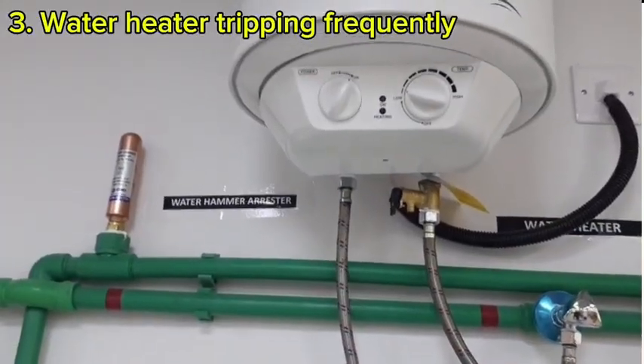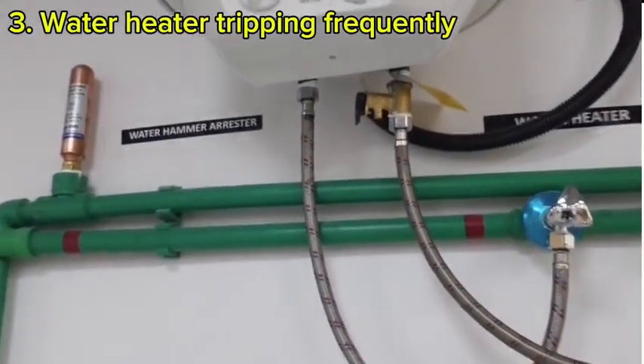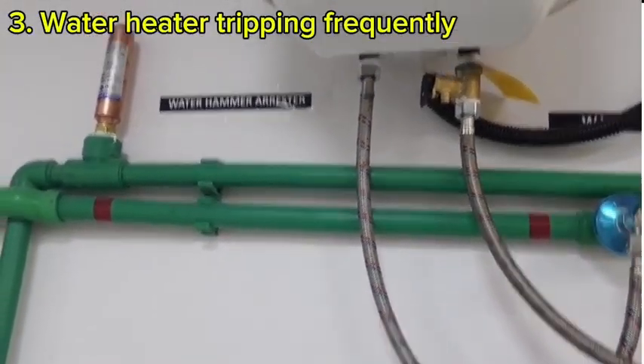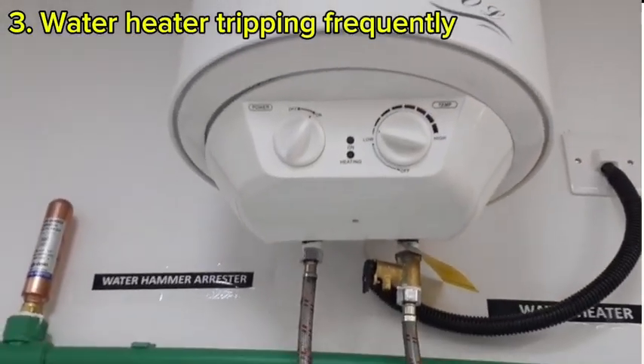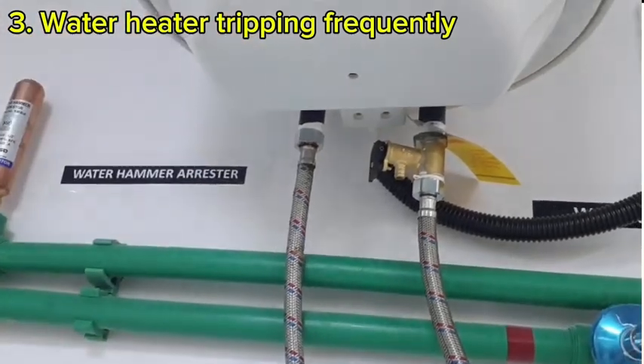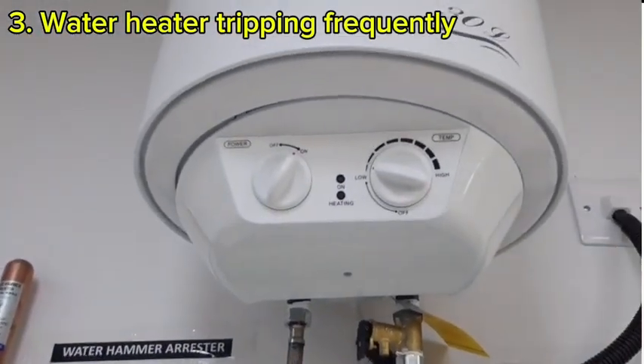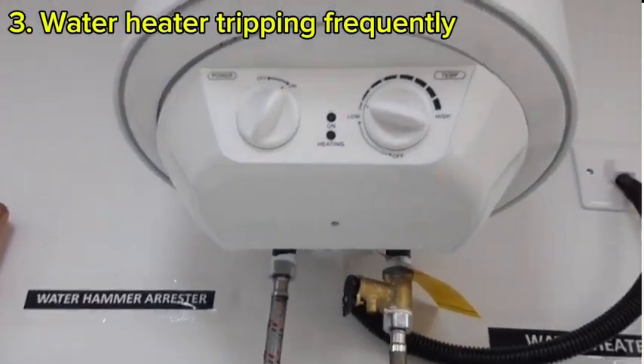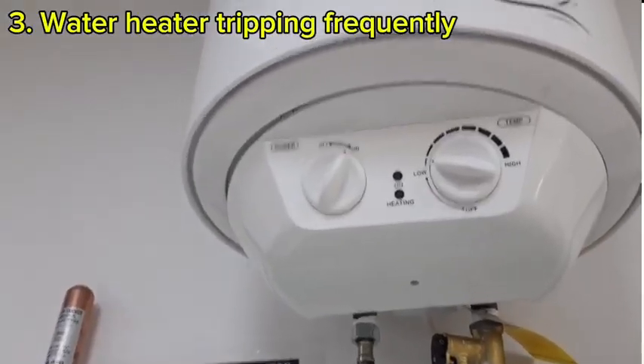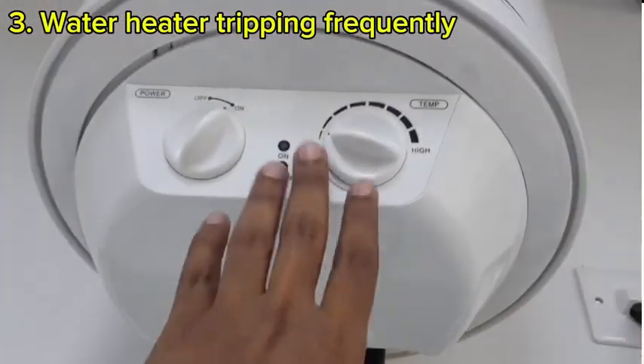Problem number 3, the water heater is tripping frequently. So why does our water heater trip frequently? We can say a faulty heating element inside, then also ground leakage, that means your earth leakage circuit breaker will trip, loose wiring, and also overheating of the thermostat inside the water heater.